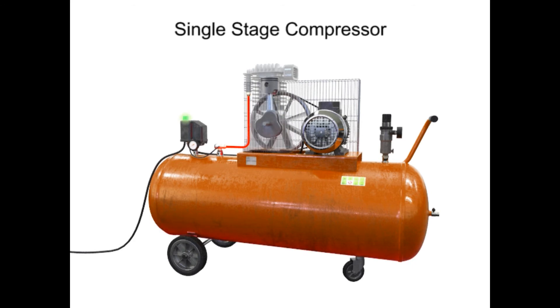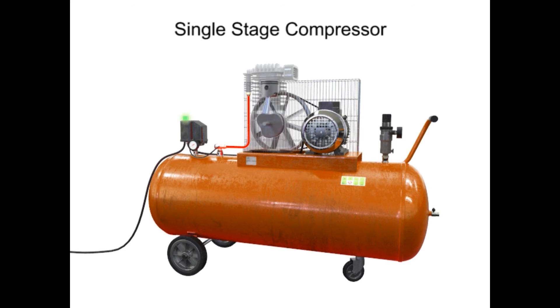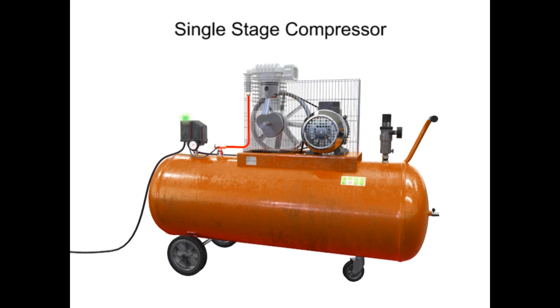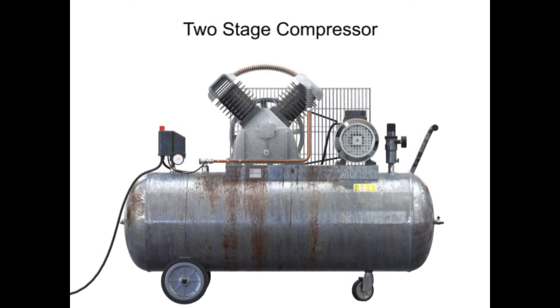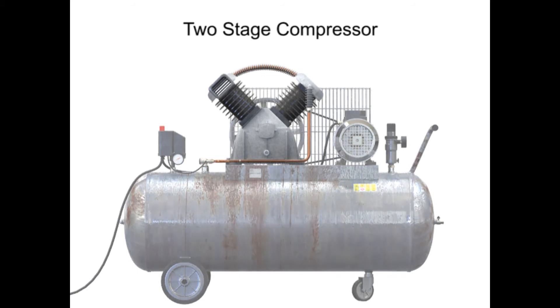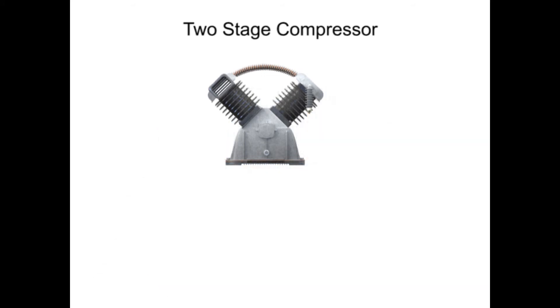If the air becomes too hot, not only is the compression cycle less efficient, but there is the hazard of an explosion if any hydrocarbon material, such as oil or lubricant, comes into contact with the overheated air. To avoid the hazards of overheating and still generate higher pressures, manufacturers make compressors with multiple stages.